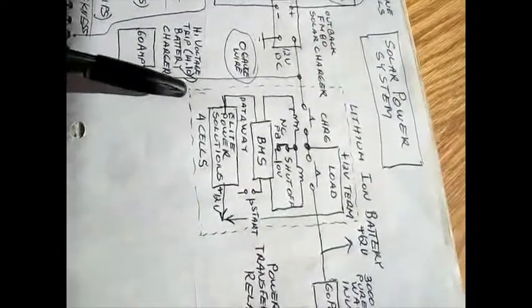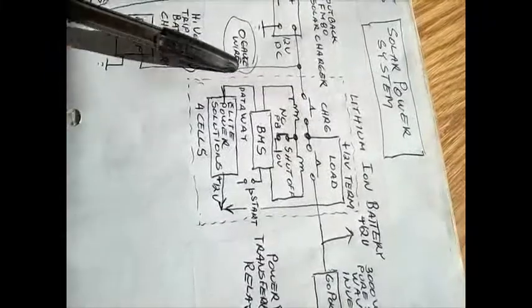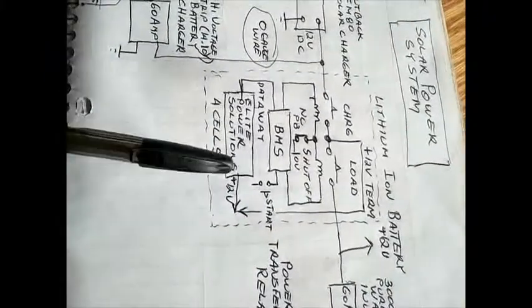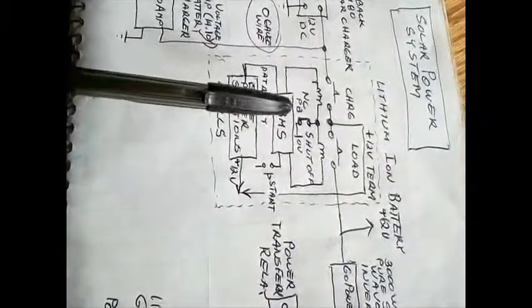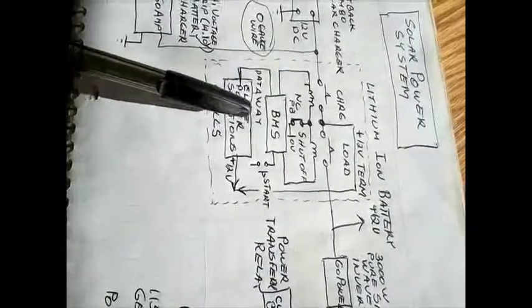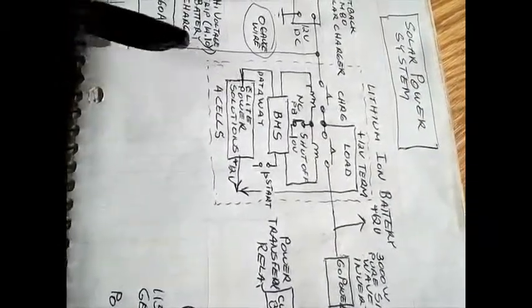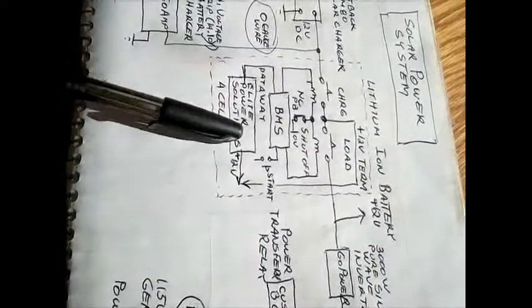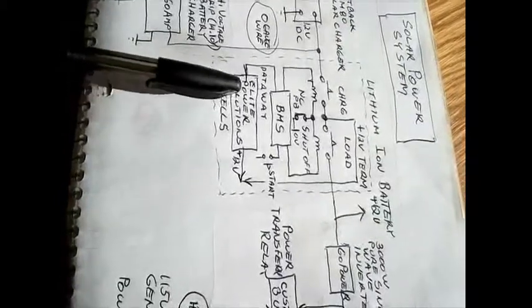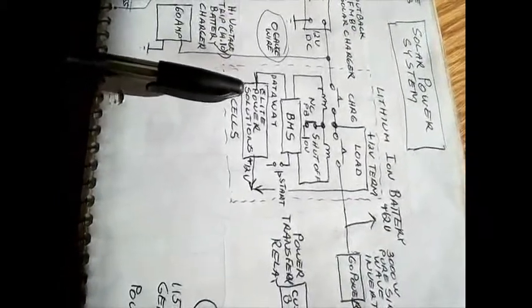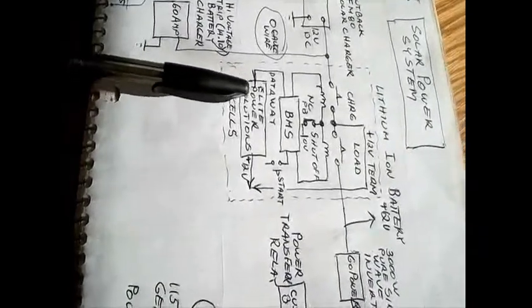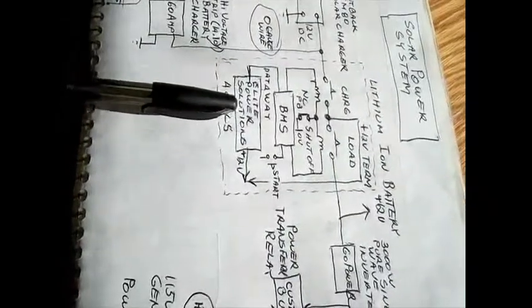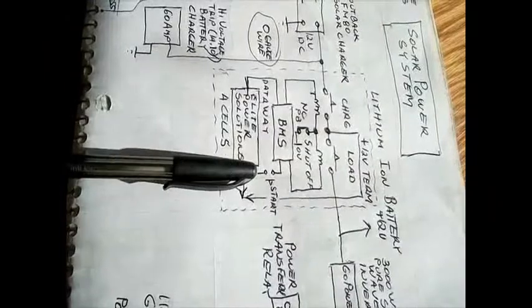So once again, I want to look at the battery itself. This is our lithium battery. Here's all the battery cells. In this case, we're using 4 cells. There's a battery management system, and the battery management system has a data way which communicates to each of the 4 bridges going across the battery terminals. What it does is it measures the voltage of each cell, it measures the temperature, and it also performs balancing of the cells, so that all the voltages of the cells are the same. That's what it tries to achieve.